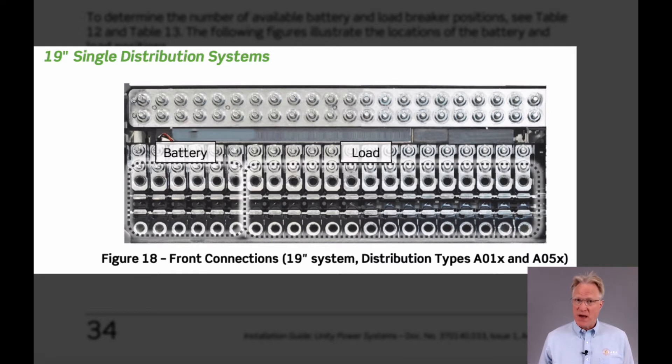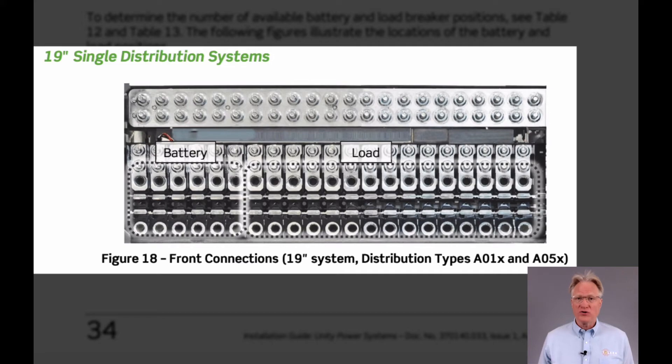The 19-inch distribution options include six battery breakers, with or without a low voltage disconnect, and 15 load breakers. If no battery breakers are needed, all 21 breakers can be load breakers.